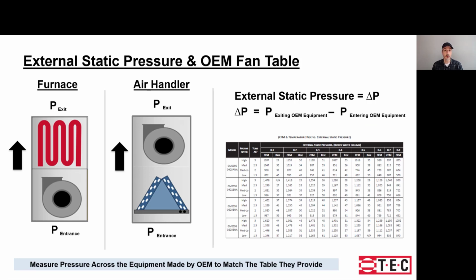or original equipment manufacturer. And so whether it's a furnace or an air handler, that might mean you're drilling near different pieces of the system, but it's always the entrance and exit to the equipment being supplied by that OEM that you're going to be measuring. So for example, on an air handler, that might be right before the indoor coil and right at the exit or right after the blower. But on a furnace, it might be right after the filter and right before the coil.